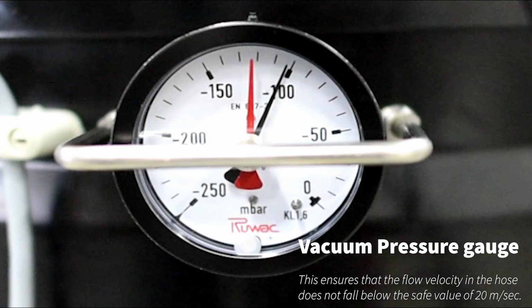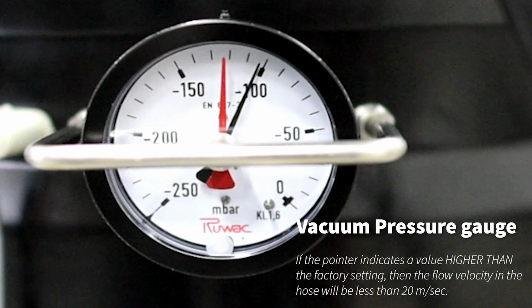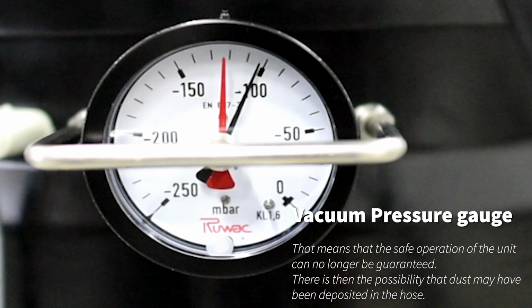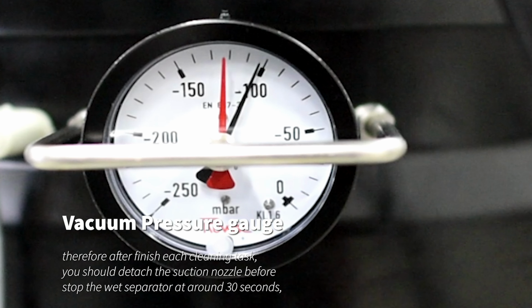This ensures that the flow velocity in the hose does not fall below the safe value of 20 meters per second. If the pointer indicates a value higher than the factory setting, then the flow velocity in the hose will be less than 20 meters per second. That means that the safe operation of the unit can no longer be guaranteed. There is then the possibility that dust may have been deposited in the hose.